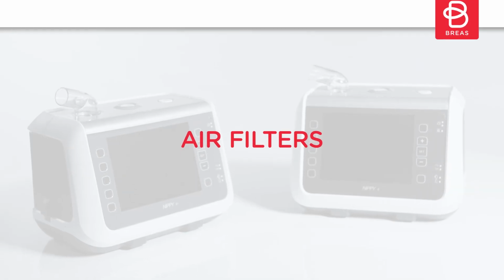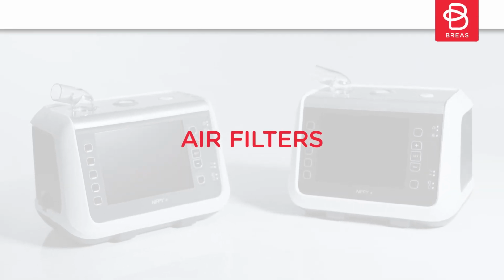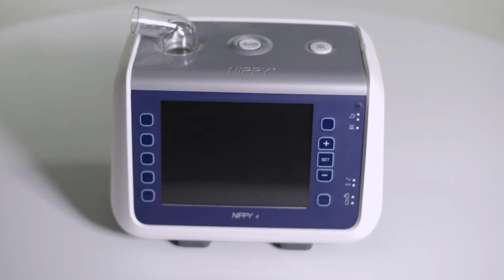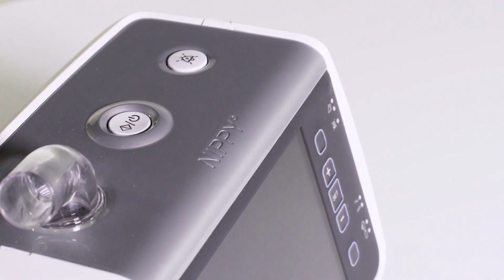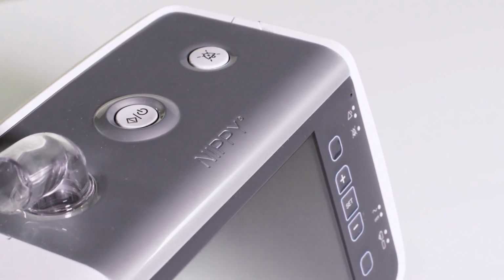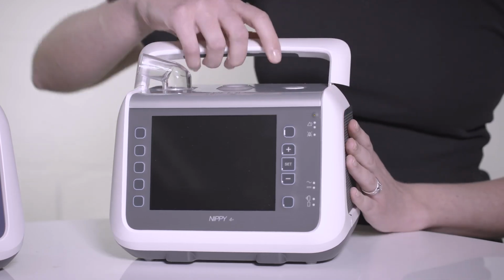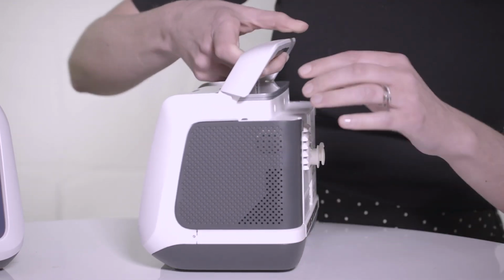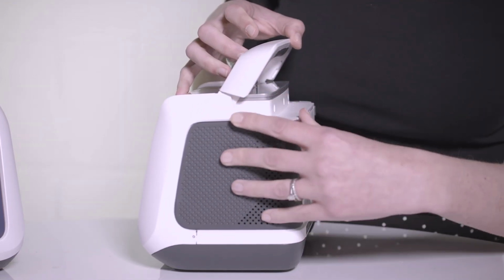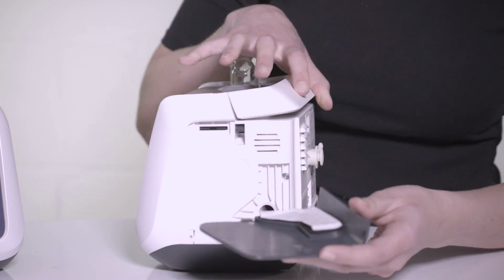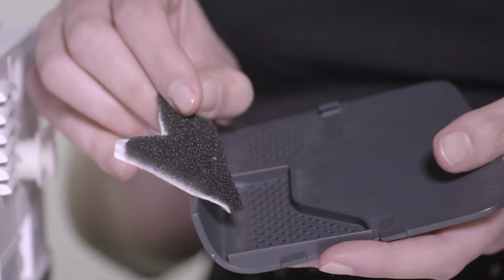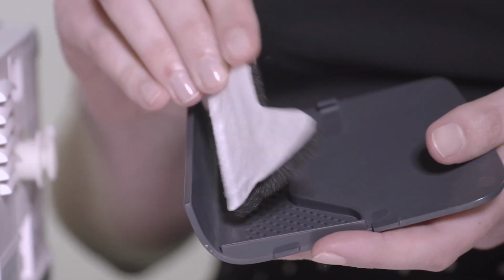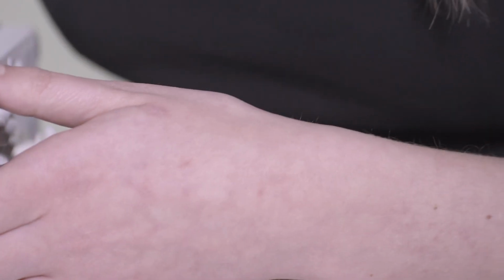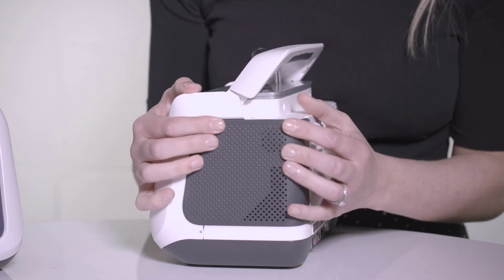Air filters. The device will draw in air from the environment, so there are some air inlet filters to protect the mechanics from dust and debris. To check the cleanliness of these filters, lift the carry handle and press the button on the right-hand side of the device to release the side panel. There are two filters, a grey one for larger particles and a white one for smaller dust particles and allergens. Check the filters weekly.